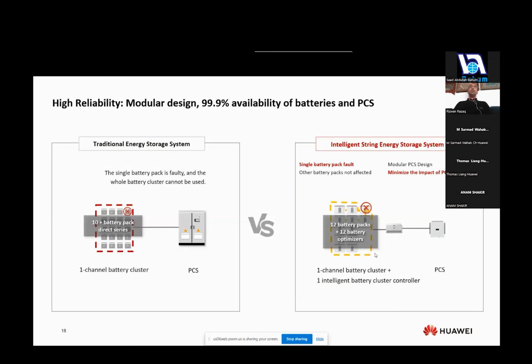So the high reliability in the modular design is providing that 99.9% availability. So what is the difference here? On the left-hand side is your typical traditional energy storage solution, where you've got one channel of batteries in a cluster, and they are then combined with a singular PCS unit, bespokely made for your particular project or at a certain rating size. On the right-hand side is your intelligent string energy storage solution.